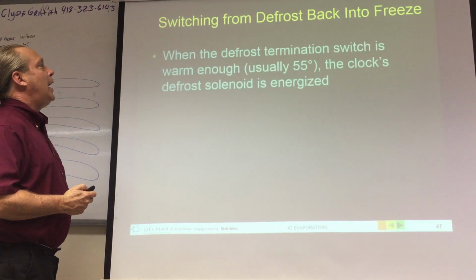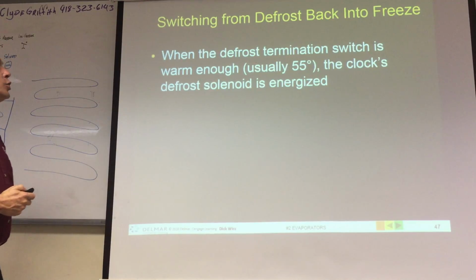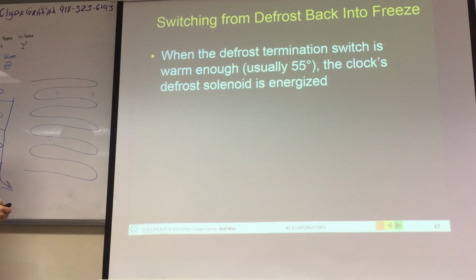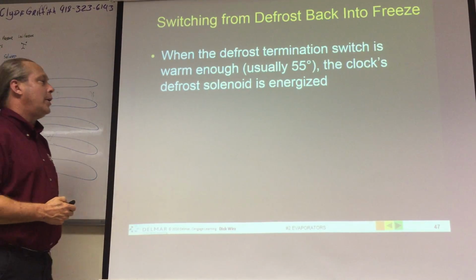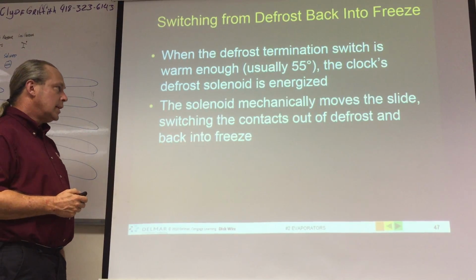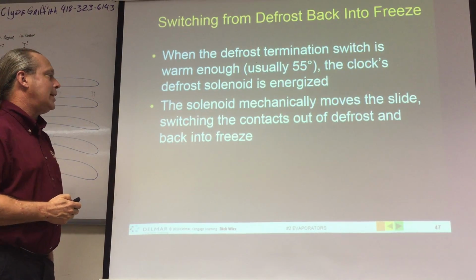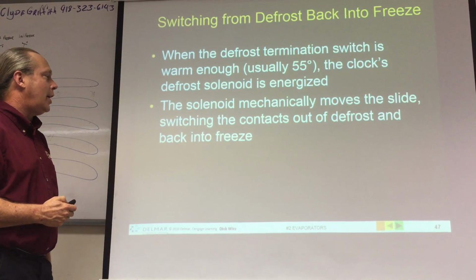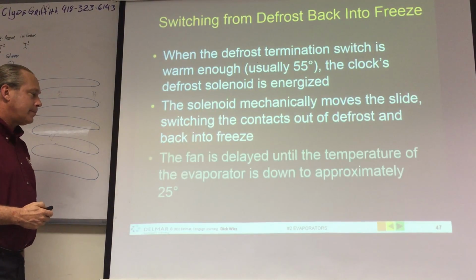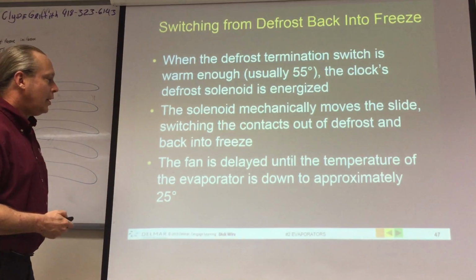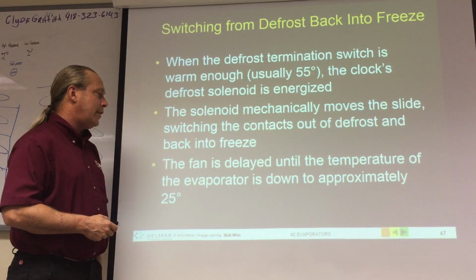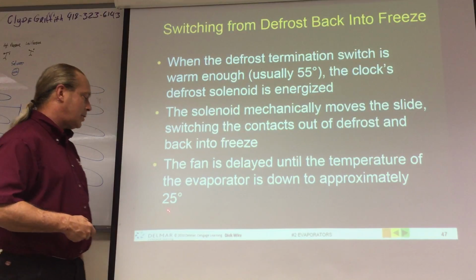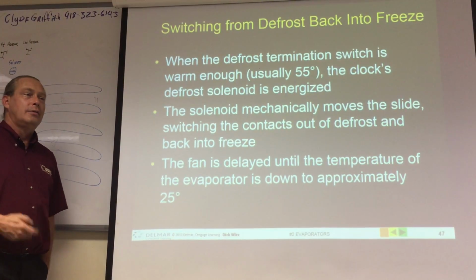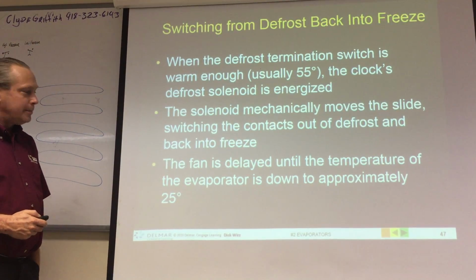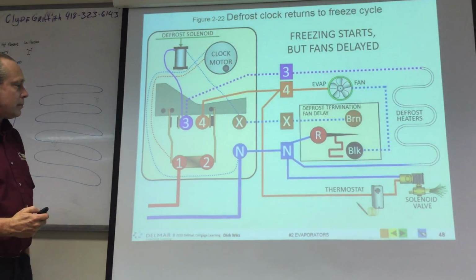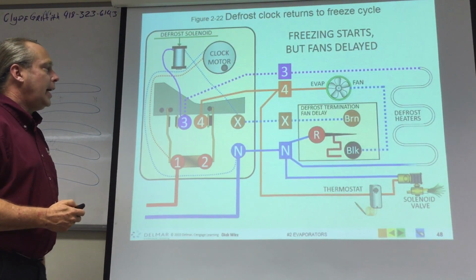Switching from defrost back to freeze. When the defrost termination switch is warm enough, usually 55, the clock's defrost solenoid is energized. The solenoid mechanically moves the slide, switching the contacts out of defrost and back into freeze, as we saw just a minute ago. The fan is delayed until the temperature of the evaporator is down to approximately 25, they say. Pretty close enough.